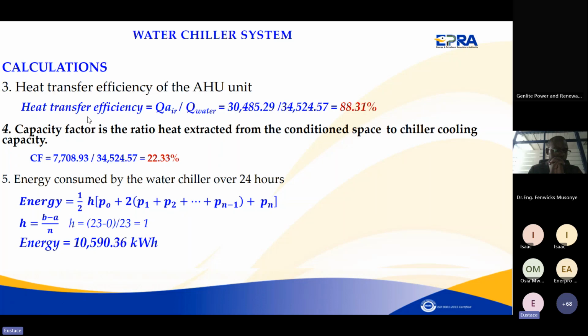You need also to get the manufacturer's specification, what the heat transfer coefficient of each AHU unit is. Or if you make a new design, if you design a new air conditioning unit, during commissioning you need to establish the heat transfer coefficient of that and set it as a benchmark. Is that clear?